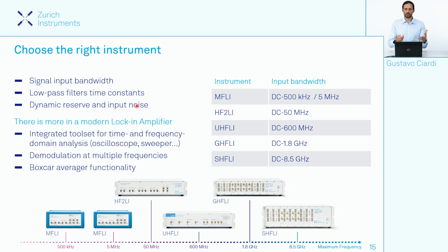The thing is, in modern digital instrumentation, there is much more than just a lock-in amplifier. There are more ingredients that might be interesting to run a more optimized experiment. For example, there can be a large range of low-pass filter constants, or a large dynamic reserve, which tells us how good my instrument is at rejecting noise. Or there might be other tools that might be interesting for my experiment, for example an oscilloscope integrated directly into the lock-in amplifier, a sweeper, the possibility of demodulating the same signal at multiple frequencies, for example first harmonic, second harmonic, and so on, and also maybe the possibility of running a boxcar averager measurement on the same device.